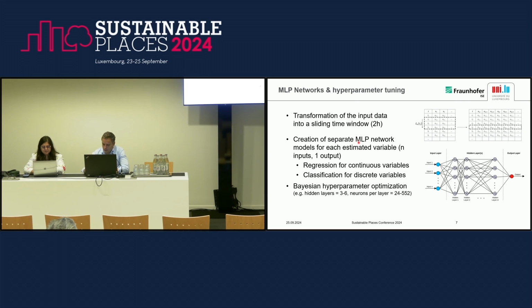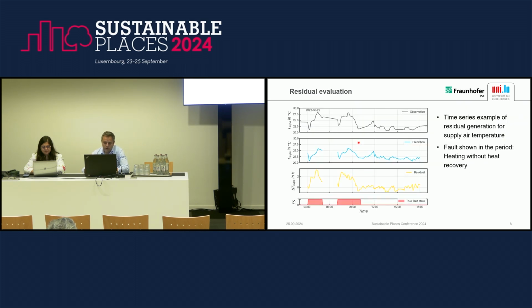At the end of the day it looks like this. It's just an example of how Sebastian generates residuals. So here you have the observed supply air temperature, here the prediction from the model, and here the residual. When this residual has a typical shape, the algorithm generates a fault state, which springs from 0 to 1.